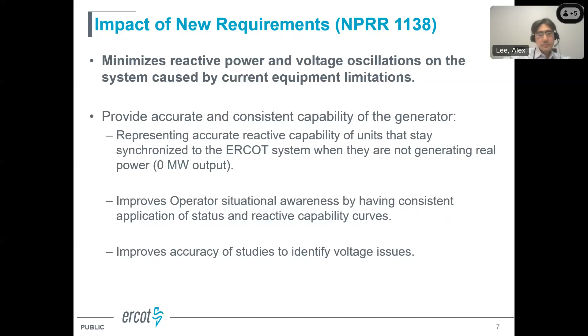On top of those new requirements, ERCOT started utilizing an oscillation detection tool provided by vendors almost 10 years ago. Over the years, ERCOT has been increasing the number of PMUs in our footprint. Currently, we have about 270 PMUs that are streamed at 30 samples per second. This is more for situational awareness and to trigger investigation as needed when oscillations happen.